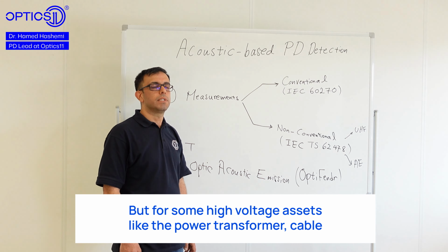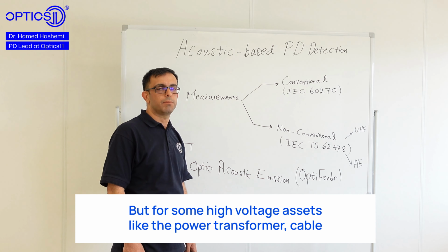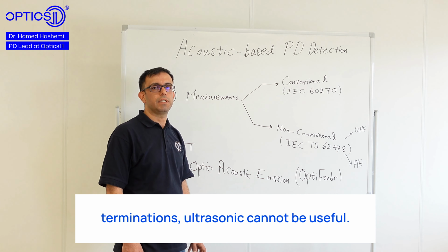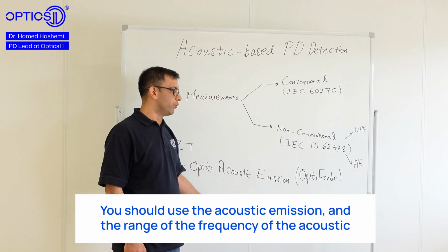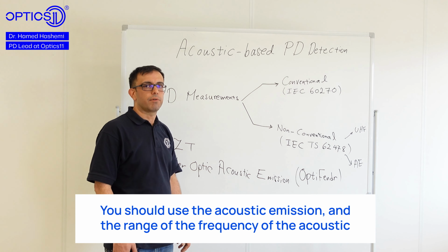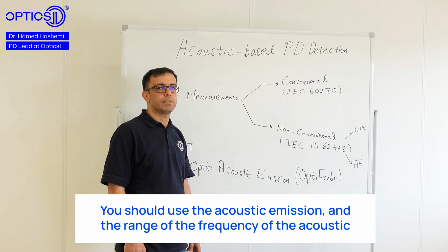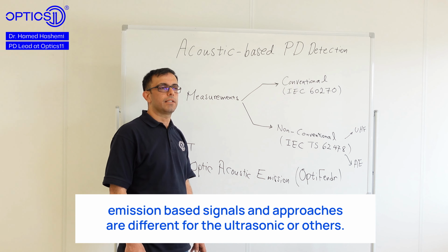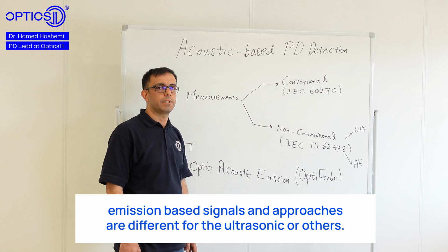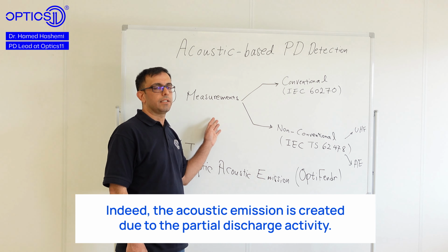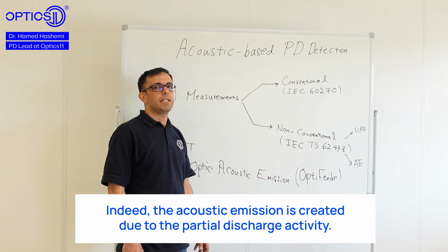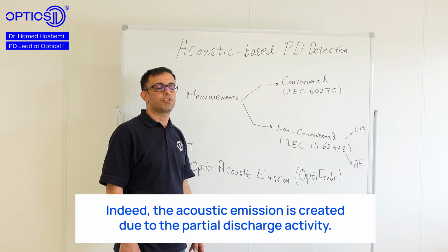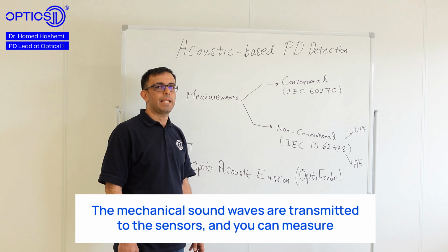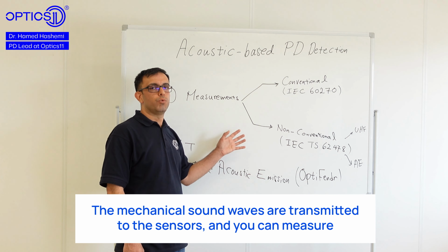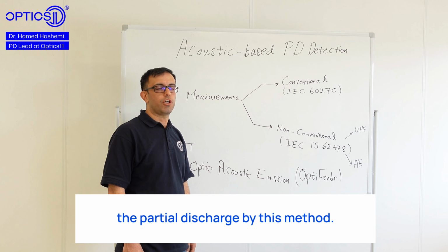But for some high voltage assets, like power transformers and cable terminations, ultrasonic cannot be useful. You should use the acoustic emission. And the frequency range of the acoustic emission based signals and approaches is different from the ultrasonic and others. Indeed, the acoustic emission is created due to the partial discharge activity. The mechanical sound waves are transmitted to the sensors, and you can measure the partial discharge by this method.